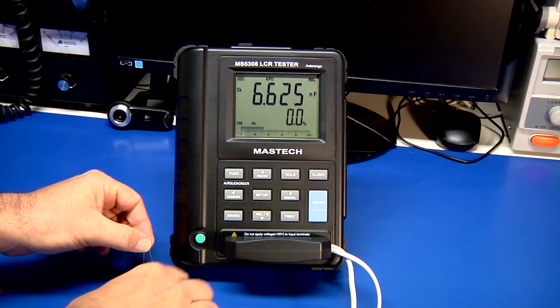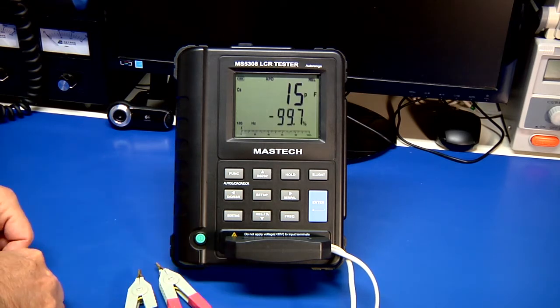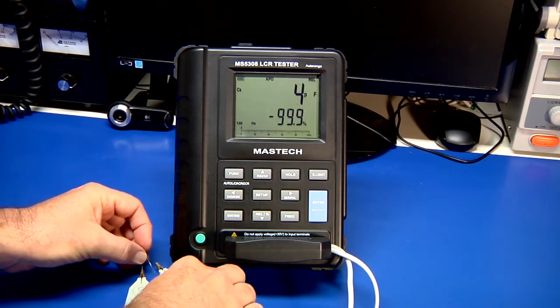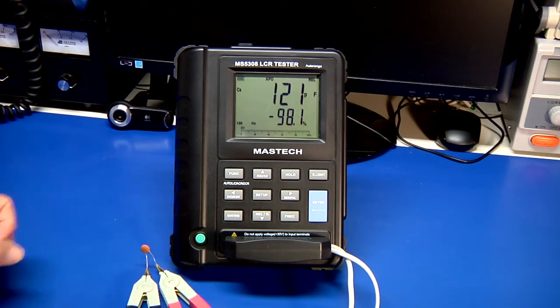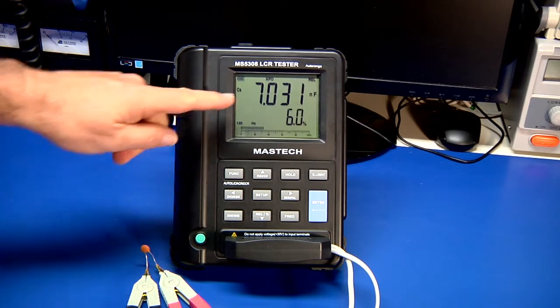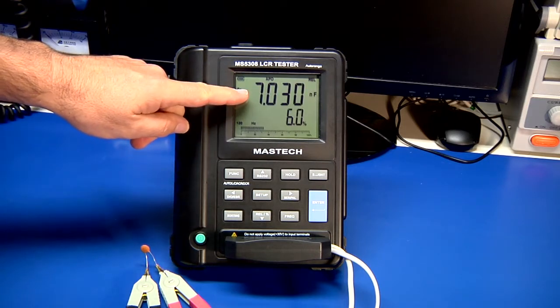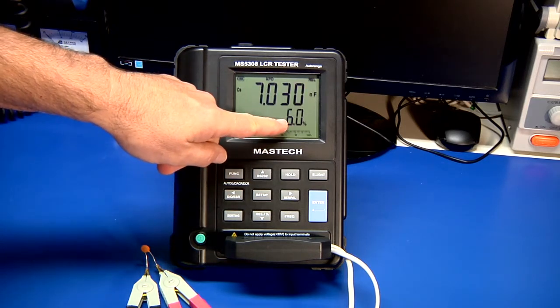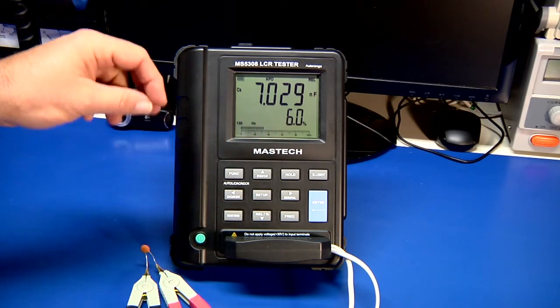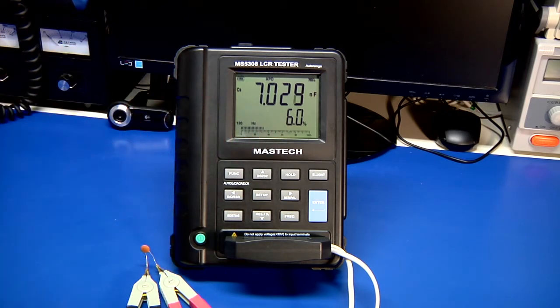So if I take that capacitor off and put in another capacitor, you can see that compared to the reference one I just had in there, it's 6% higher. You can cycle through and get percentages, and again, this will do plus or minus 99%.